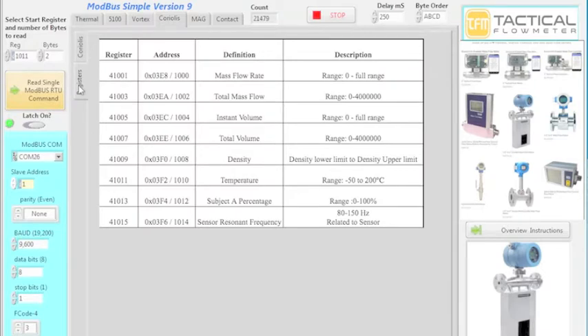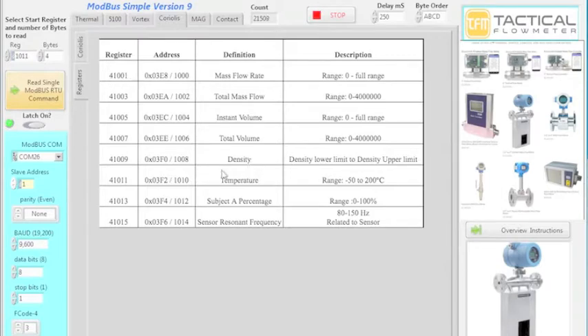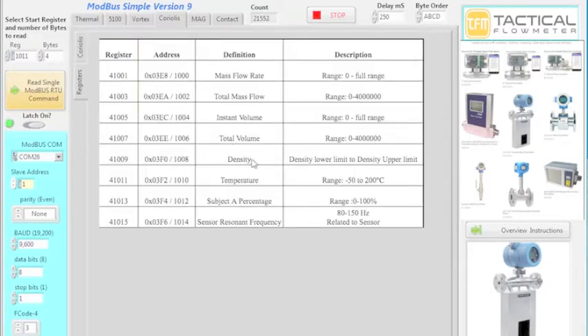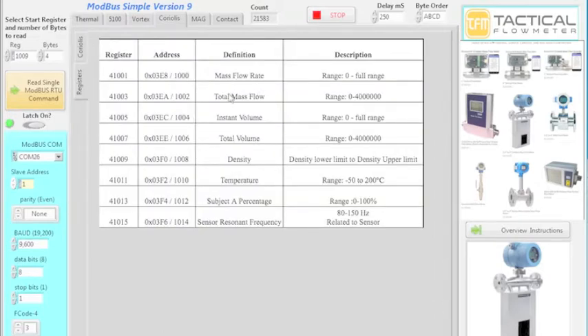Now let's look at reading something like the totalizer, or medium density. Density is register 1009 — I need to show all 4 bytes that make up a float. The address for temperature is 1011. In A, B, C, D byte order with no parity, slave ID 1, 9600 baud, 8 data bits, 1 stop bit, and FC code 3. Let's spy on medium density at register 1009 — it reads 1.2, which is what we put in earlier. We can also look at the totalizer at register 1003.